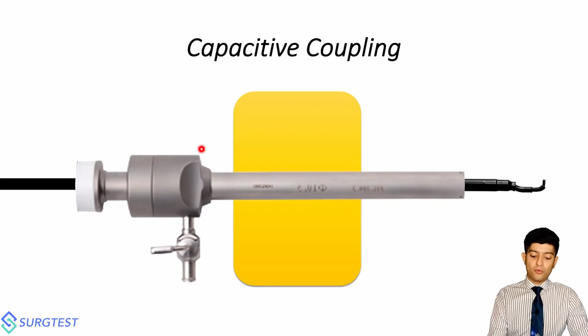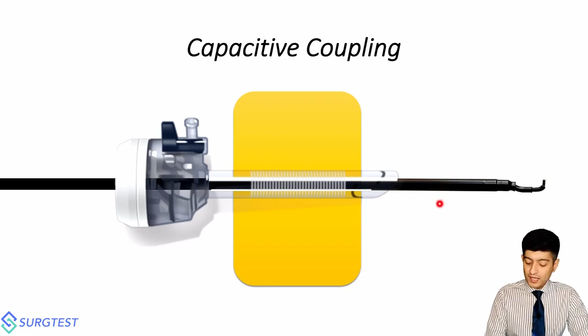But imagine we are using a disposable plastic non-conducting trocar. Well, now we don't have any capacitor in play, right? Because we only have the insulation with the conducting area within. But sometimes these disposable trocars end up having a faulty valve, and we'll end up using a metal reducer within them to take care of the CO2 leak which is happening. Now do you see how a capacitor has been created? Additionally, because of the insulation that is provided by this plastic trocar on the outside, this non-conducting sleeve, the charge cannot be dissipated across the abdominal wall. Instead, the tip of the metal trocar can now come into contact with any of the surrounding visceral structures and disperse the energy that is built up within the capacitor, and this is termed capacitive coupling.